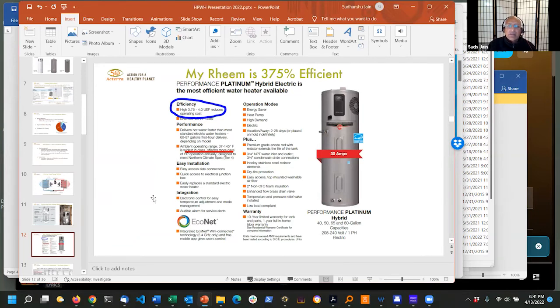With electric resistance, they will do 30 amps at 240 volts, so that's about 6.5 kilowatts, which you can convert to BTUs. The circuit that runs an igniter should be a 15 amp circuit. The 120 volt heat pump water heaters will run on a 15 amp circuit. I don't think anyone runs anything less than a 15 amp circuit, but if you have a lot of other things on that circuit, you'd have to run a dedicated line or split up your line. But your wiring should be capable of running a heat pump water heater if there's nothing else on there.